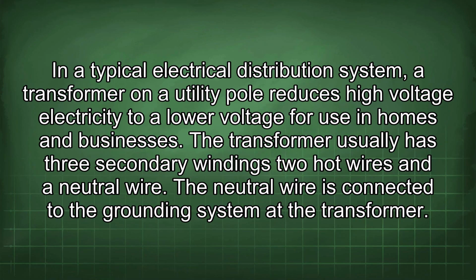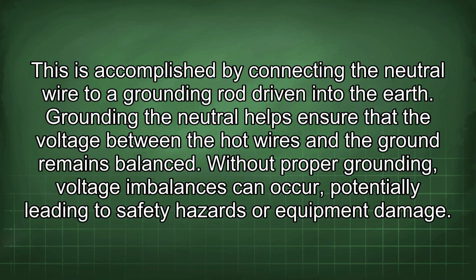In a typical electrical distribution system, a transformer on a utility pole reduces high-voltage electricity to a lower voltage for use in homes and businesses. The transformer usually has 3 secondary windings, 2 hot wires, and a neutral wire. The neutral wire is connected to the grounding system at the transformer. This is accomplished by connecting the neutral wire to a grounding rod driven into the earth.